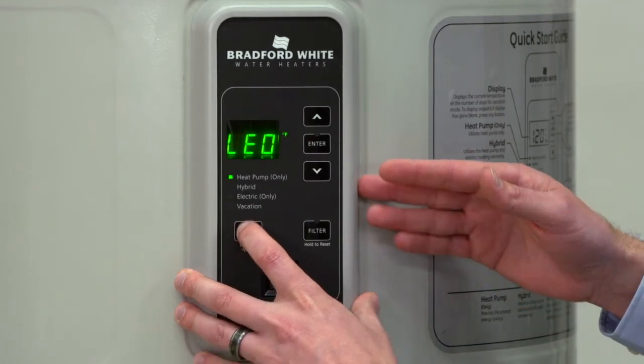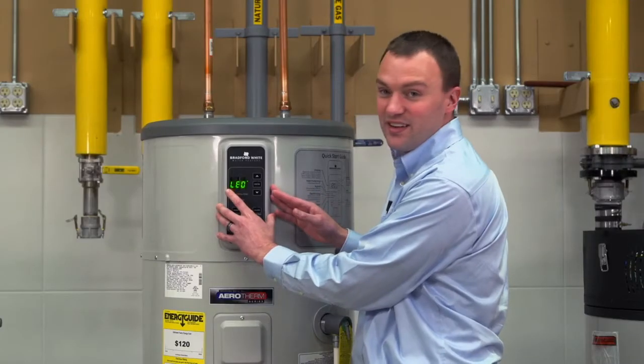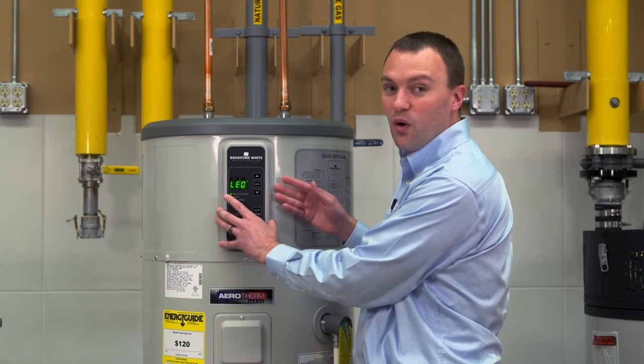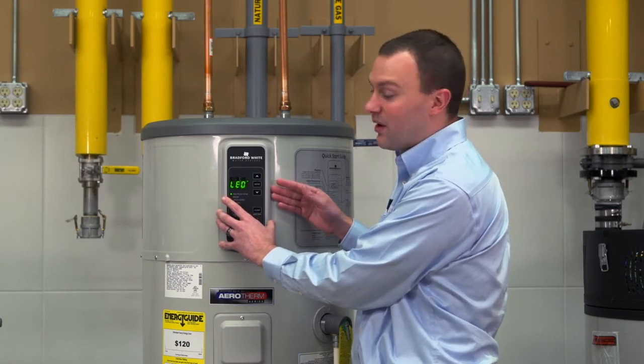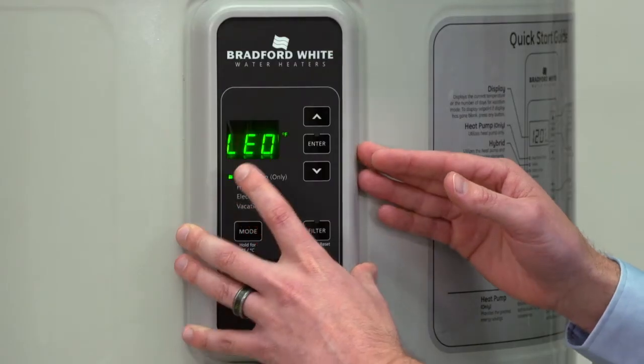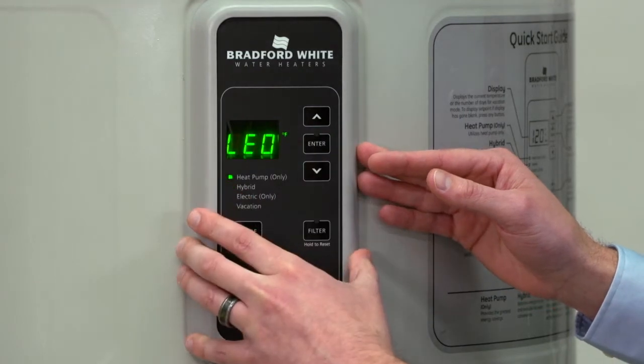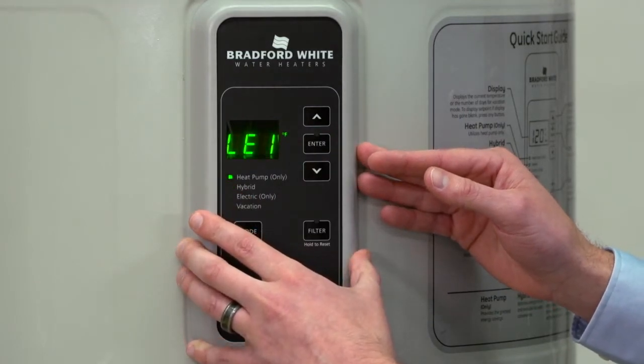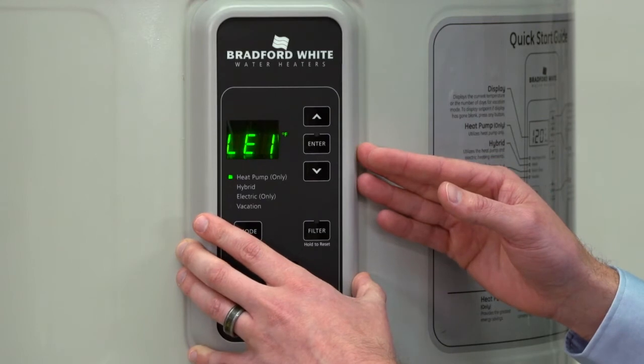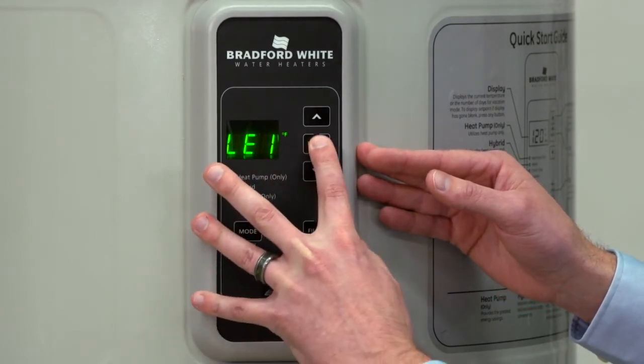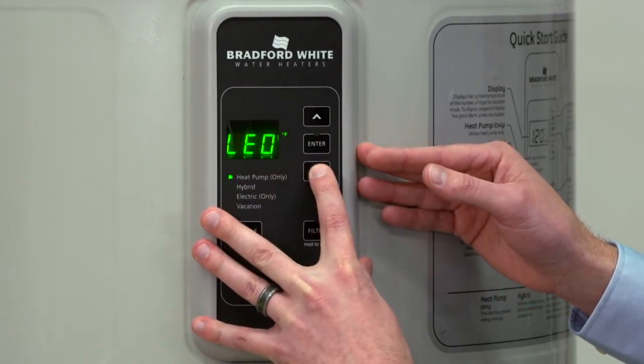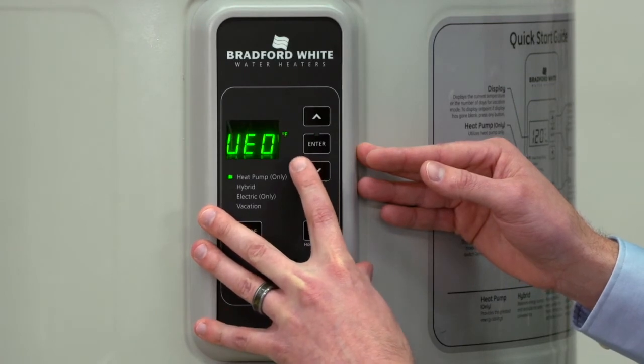The first screen that comes up is LEO. So LE is going to be lower element. The O is going to indicate off. So I'll hit the enter button to turn the element on. You'll see the 1 comes up to indicate that the lower element is now engaged. So we'll turn that off, and we'll use the down arrow to go to the upper element.